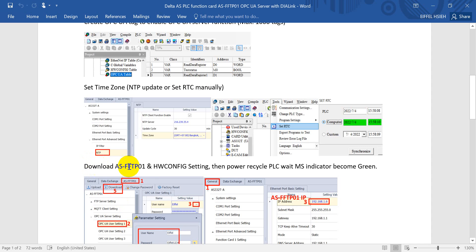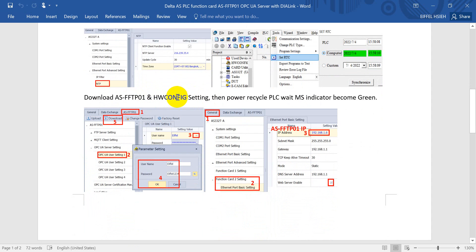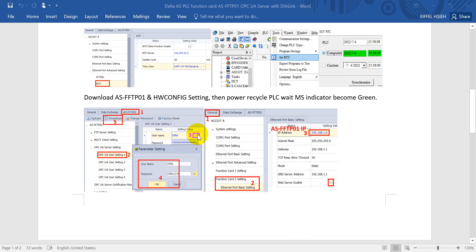Next I will talk about the hardware config setting of OPC and FTP function card. To set the IP address of a function card, go to the Function Card Tool. You can see we set the IP address here. By default, the web server function is enabled. Next, click the FTP function card, then click OPC UA user setting to enter and set the username and password. In today's example we use username 'i4' and password 'i4-1234'.